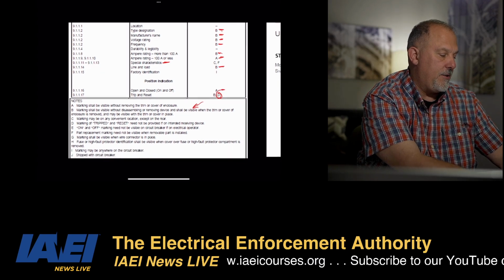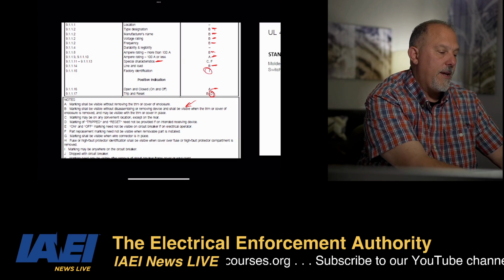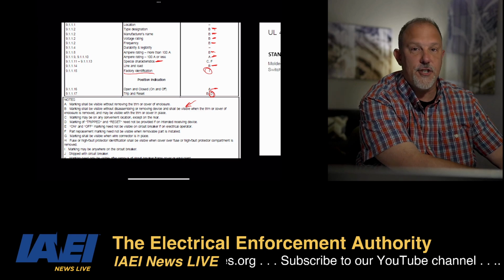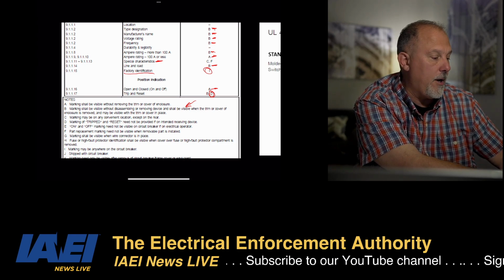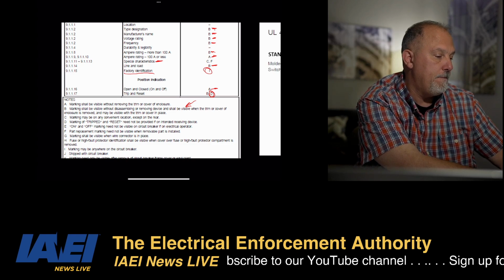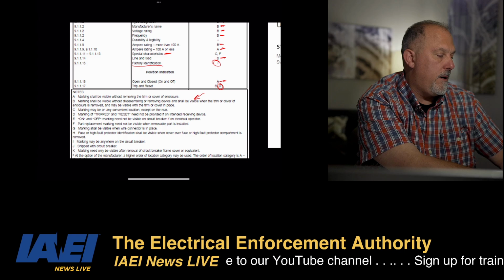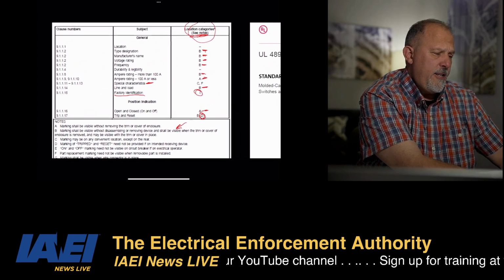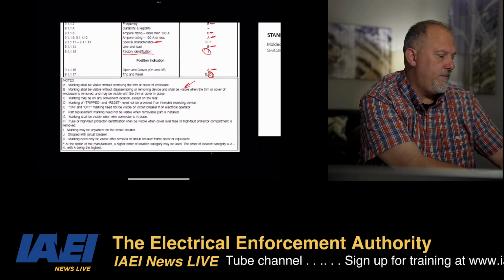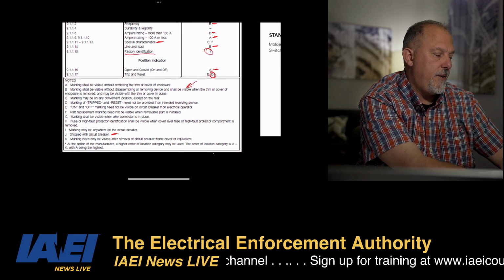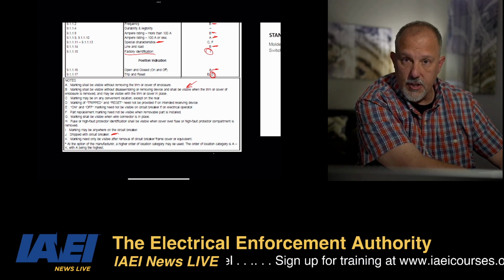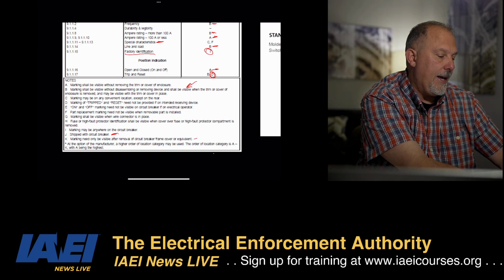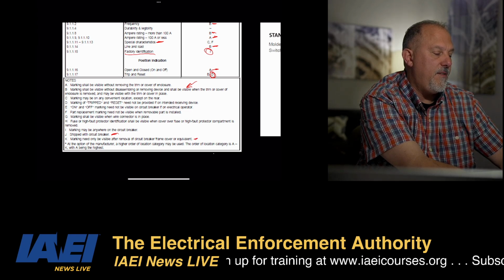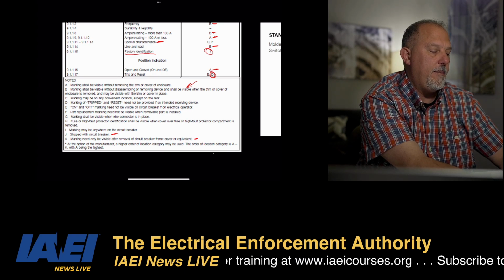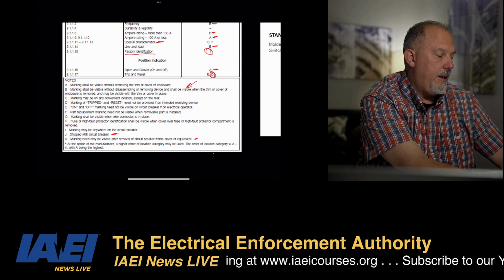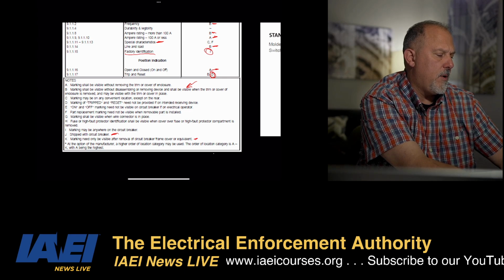Oh, there's an I too. Marking may be anywhere on the circuit breaker. That's the I, that's the factory identification. You can put that factory identification anywhere, but it has to be on the circuit breaker. There's a J, which isn't in the table up above, but a J is shipped with the circuit breaker, so that means it could be on the instruction leaflet and whatnot. K is marking needs only be visible after removal of the circuit breaker frame, cover, or equipment. And then I think we cover them all.